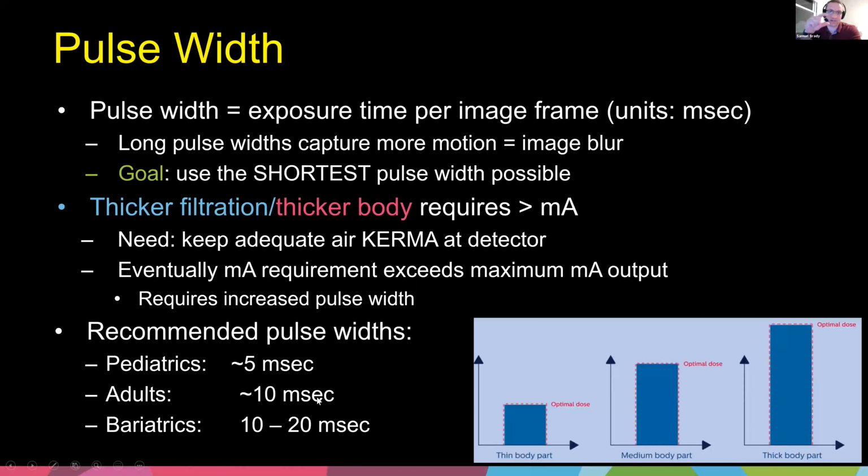So you take the same block of plastic, for example. Let's say you take 15, 20 inches or centimeters of plastic. You put it in your X-ray tube between the tube and the detector, and you image it, and you put your solid state detector in there, and it'll measure the waveform. A lot of the mobile C-arm systems are somewhere in the 20 to 30 millisecond range.